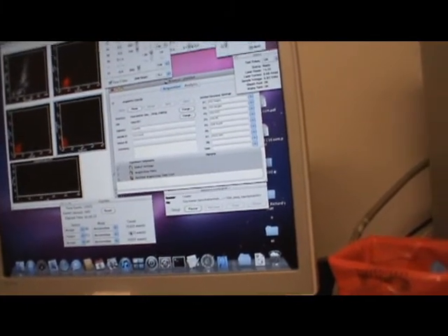It's acquiring. You can change the file name, say unstained.11, or anything you like. Once it reaches 10,000 events, I can put it on high. Once it reaches 10,000 in this gate, it should automatically stop, because we have already given the command to stop. Otherwise it keeps going. It's telling you events per second, a lot of cells. And see, now it has stopped.